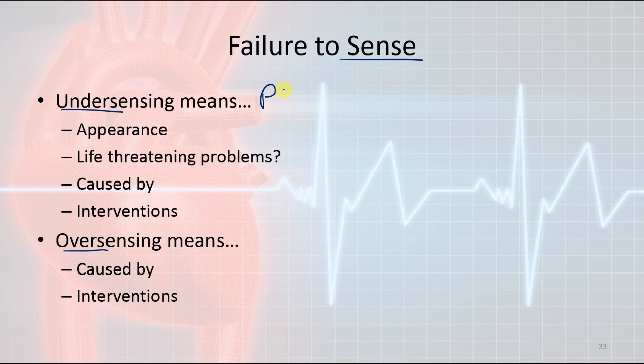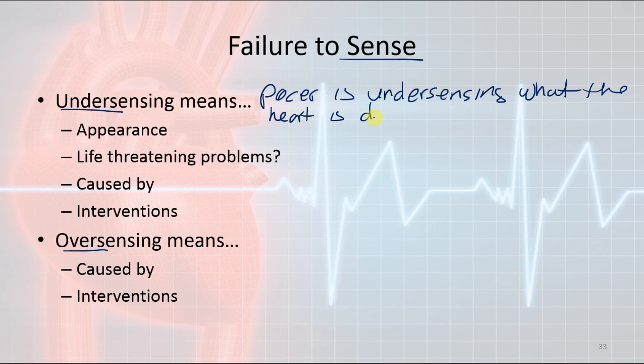Undersensing means that the pacer is undersensing what the heart is doing, which means it is not sensing what the heart is doing. So what that means is you'll have your normal P, Q, R, S, and T's, but the pacemaker doesn't detect P waves or T waves or S or QRSs. It's not detecting the electrical components of the heart, which is a problem because that means that the pacemaker is still going to depolarize, which can cause life-threatening problems.